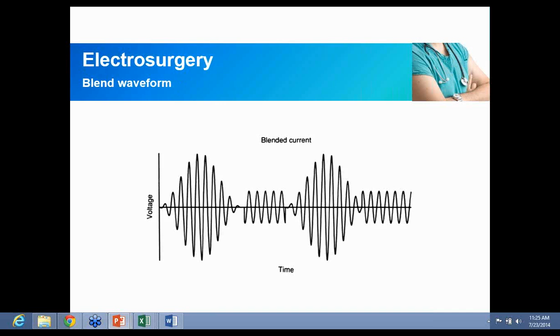Now, this is the toughest waveform, the most complex waveform, and you need to know this, because this mode creates the greatest amount of HF leakage. Even though the coag wattage might be only 120 watts, a cut waveform at 120 watts produces much less HF leakage than a coag waveform at 120 watts.